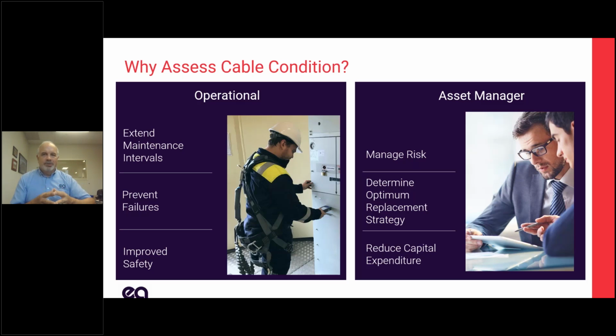So testing cables helps from an asset management perspective, where we're planning, and it also helps from the operational side. Maybe I find a cable that's bad or potentially going to fail, and I can't take it out of service. That's always difficult. I can't replace it right now. But what I can do is have termination kits, have trained joiners on call, and have spare cable, so that if it does go, I'm ready for it. That's a big thing. People say, why test my cables, because I can't change them out anyway? No, but you can be ready for the ones that potentially might go.